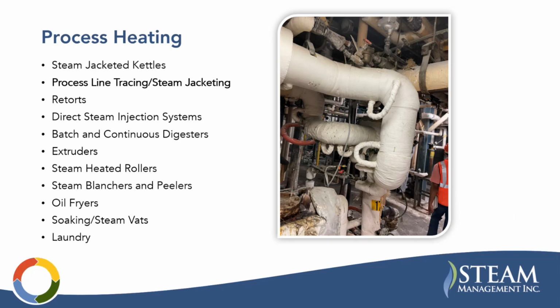So you have steam jacketed kettles, which indirectly heat and mix products using steam filled jackets around like a kettle or tank. You have process line tracing or jacketing, which maintains fluid temperature or prevents freezing in pipes. And that's what's pictured here. So these sections of the piping, they have basically an inner pipe and an outer pipe, and in between the pipes is like a steam jacket to maintain temperature.